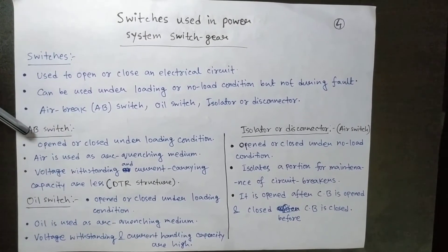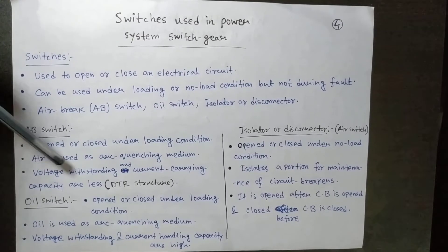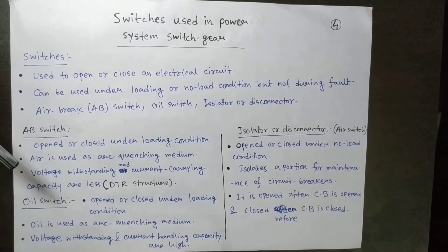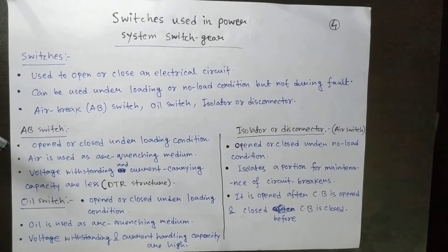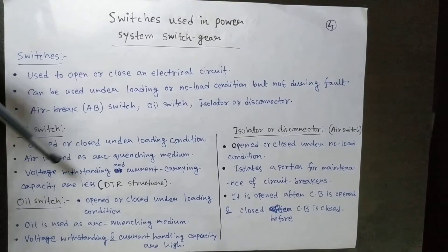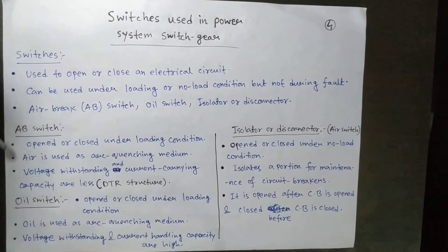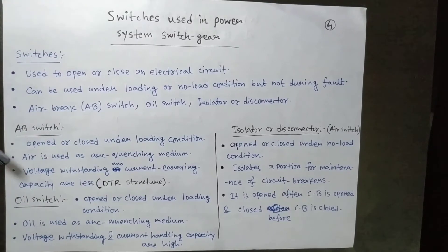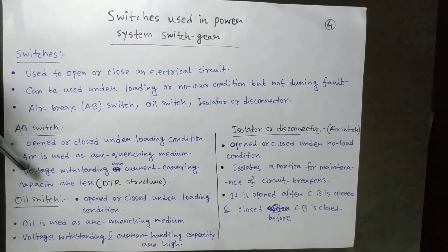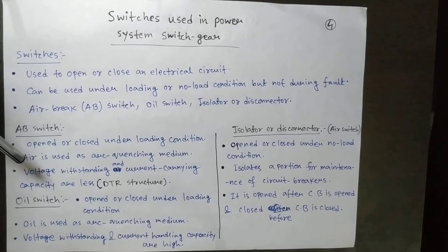The air brake switch, or AB switch, is opened or closed under loading condition. Air is used as the arc quenching medium. Although it operates under normal full load or half load conditions, arc phenomena may still occur during the opening of the switch, and air is used to quench that arc — that is why it is called an air brake switch. The voltage withstanding and current carrying capacity are relatively less because air is used as the arc quenching medium, which carries an insulation risk at higher values.